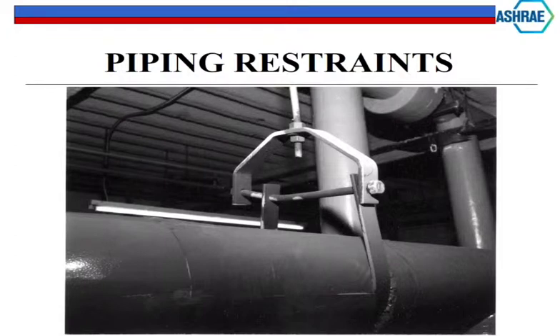Here's another problem we found with the actual connections holding up the pipe. That's a standard pipe clevis that you can buy anywhere in the world. There are no such things as heavy-duty pipe clamps or anything like that. This is basically what every HVAC contractor uses in the world. During the earthquake, this jumped up and hit the center of this bolt and bent the bolt up. Then the whole system came back down, and this side of the clevis just slid down to the lowest point possible. So now you've got to replace that.